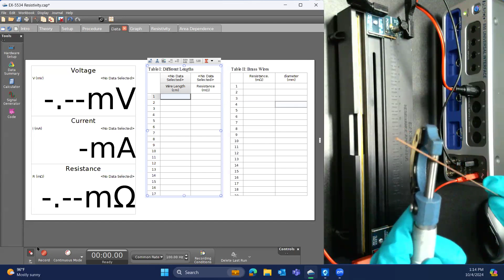So when setting this up, I just like to insert it through one end. Make sure to loosen and make sure that the sliding probes are parked up on these plastic tabs here so that you can slide the wire through without them getting caught. It's very important that your wire is very straight also, because any bends in the wire will create points of altered resistivity compared to a straight wire. And a bent wire is more difficult to read the actual length compared to a straight.